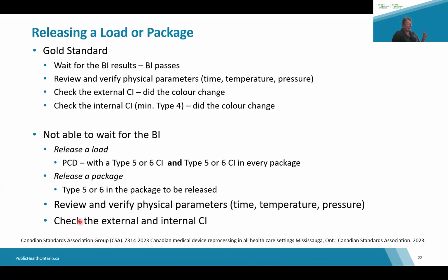If you only wanted one package out of that load and you're going to wait for the BI for the rest of them, you could have a type 5 or 6 in the package to be released. And again, review and verify all the physical parameters. And of course, check that the chemical indicators for that particular package have passed.